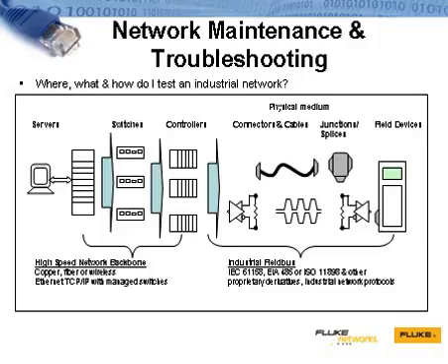As we move into the FieldBus medium, the critical measurements here surround the physical characteristics of the cable. Parameters such as connectors, opens, shorts, cabling length, or measurements of impedance, capacitance, and grounding connections are important. And then at the far right, on the FieldBus signaling level, it is the integrity and quality of the signal that we're measuring. And measurements such as amplitude and device supply level, noise, and distortion can all affect the overall quality.